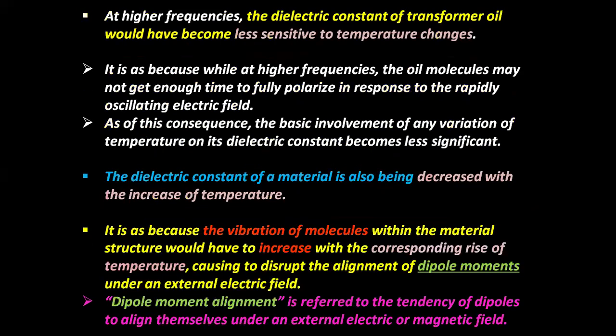At higher frequencies, the dielectric constant of transformer oil becomes less sensitive to temperature changes. This is because at higher frequencies, the oil molecules may not get enough time to fully polarize in response to the rapidly oscillating electric field, so the effect of temperature variation on the dielectric constant becomes less significant.